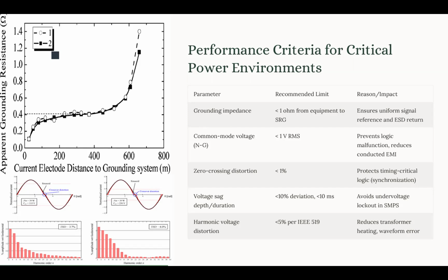Now, we also have a performance criterion for voltage sag depth and duration. The depth of the voltage sag should be less than 10% of the nominal voltage. We shouldn't have more than 10% of the nominal voltage in voltage sag, and the duration of that voltage sag should not get to 10 milliseconds or higher.